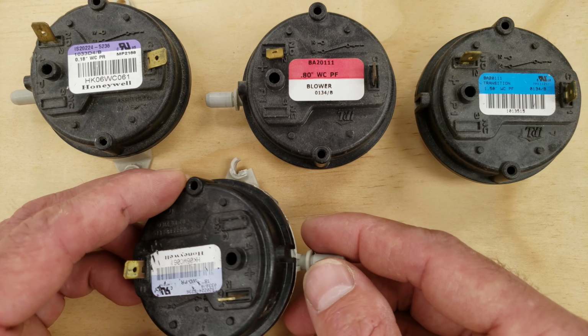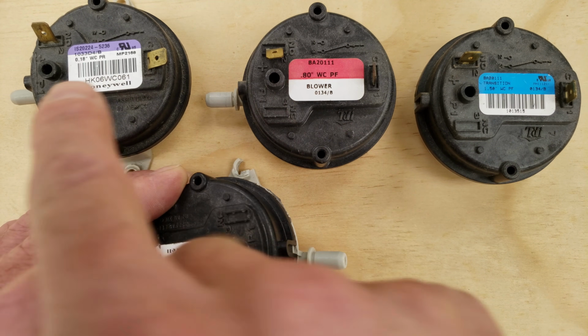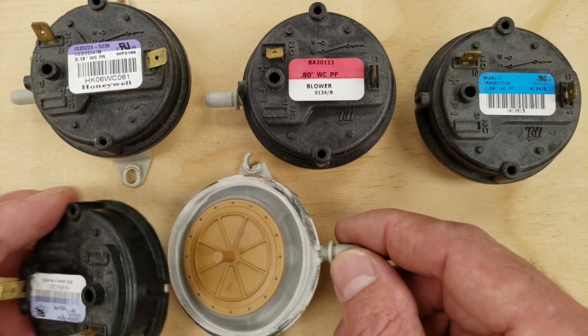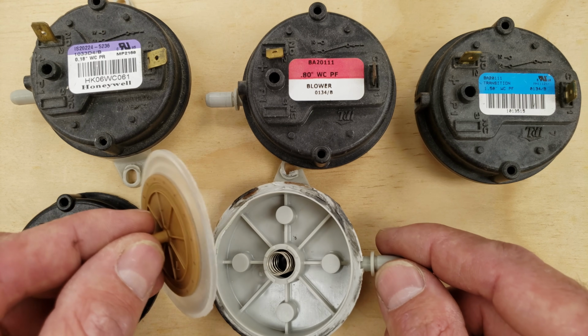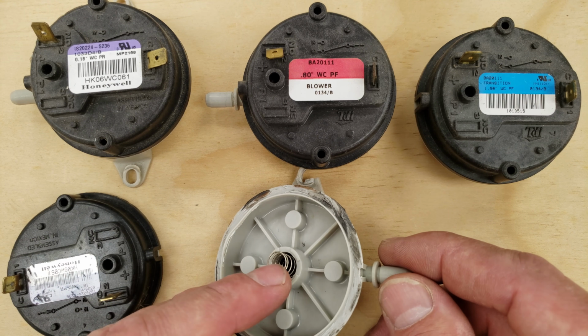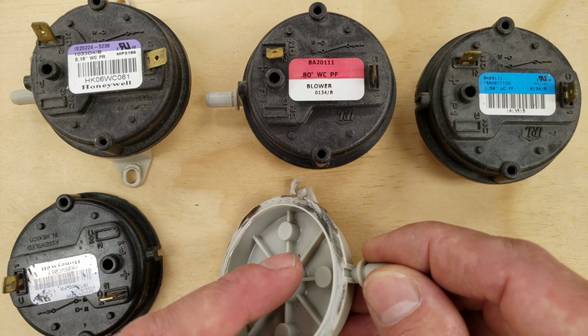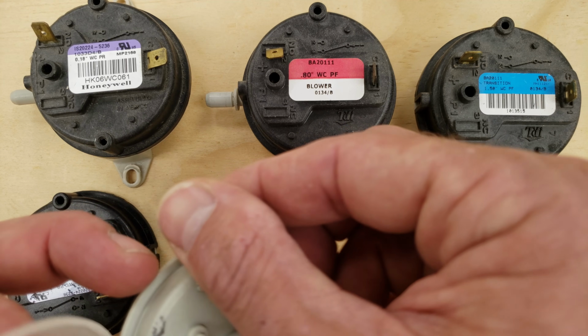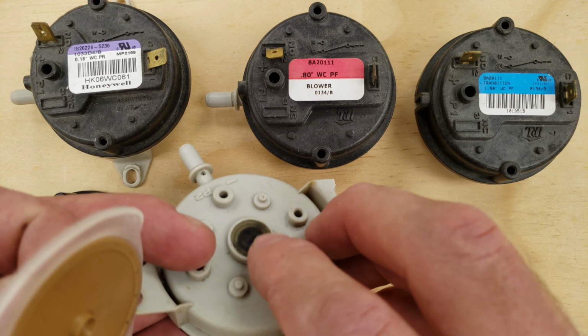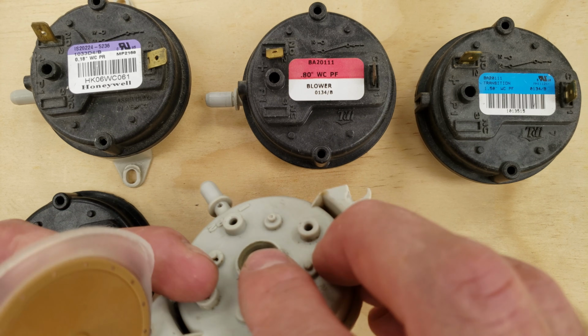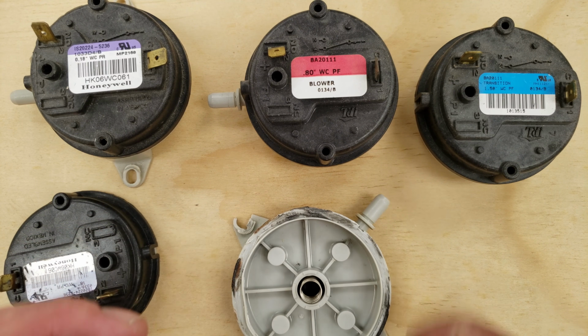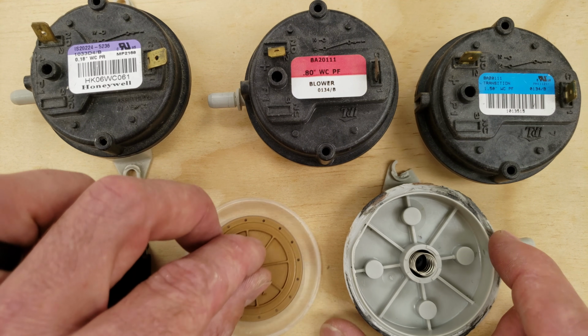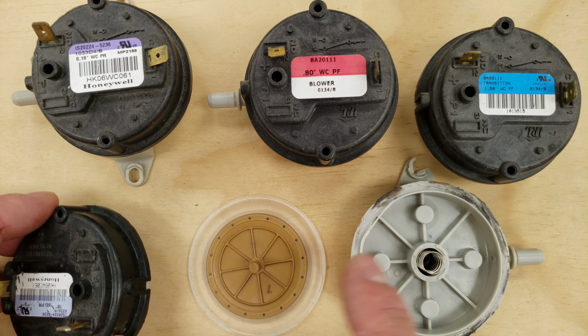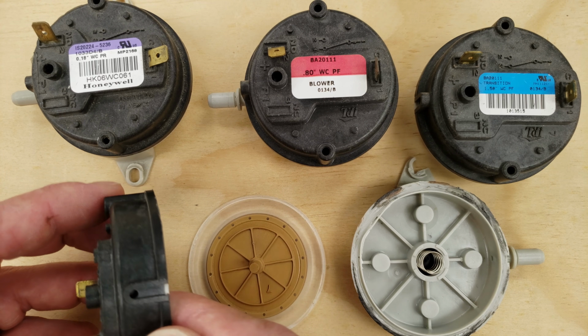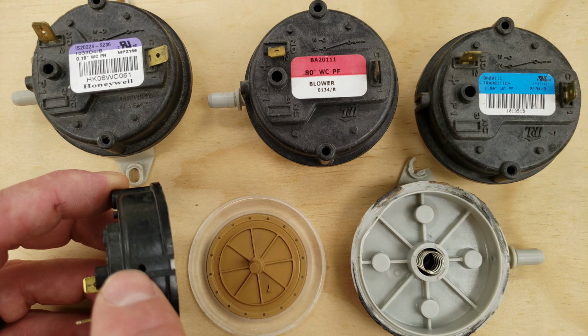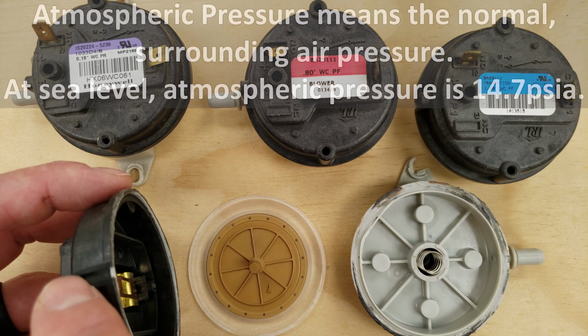So what you need to realize is this pressure right here is actually the amount of force that this spring is pressing up on the diaphragm with. So that spring right there. And that's why with these fixed pressure switches you have glue on the back, and so the set screw is kind of fixed in place. And right here you have the diaphragm separating this chamber from this chamber. And you see this hole right here? This is always atmospheric pressure, so you have that little hole.